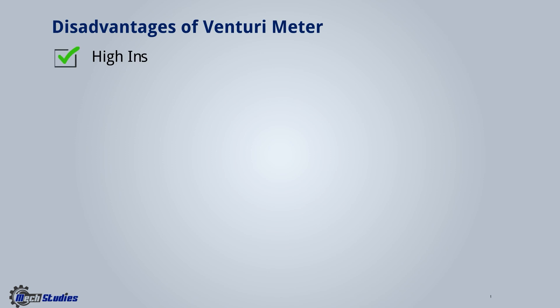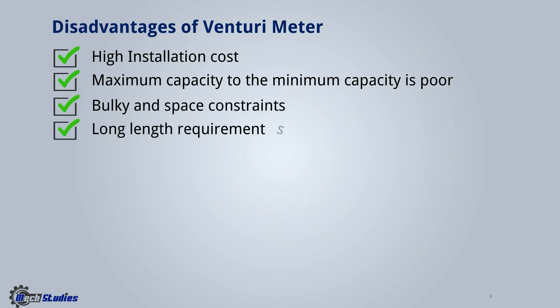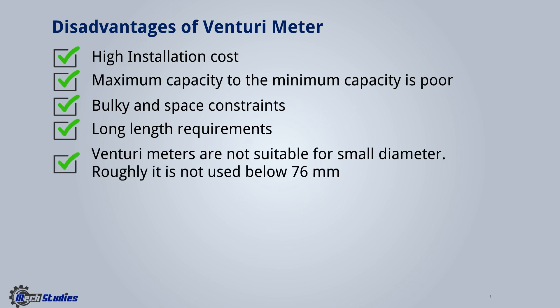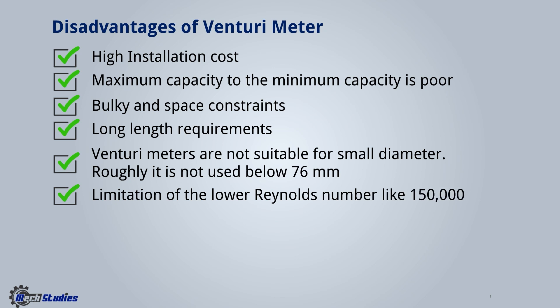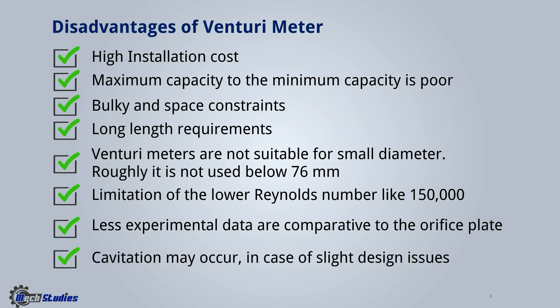Disadvantages of Venturimeters include: very high installation cost; poor turndown ratio (maximum to minimum capacity); bulk and space constraints; long length requirements; not suitable for small diameters — roughly not used below 76 mm; limitation of lower Reynolds numbers around 150,000; less experimental data compared to orifice plates; and cavitation may occur in case of slight design issues.